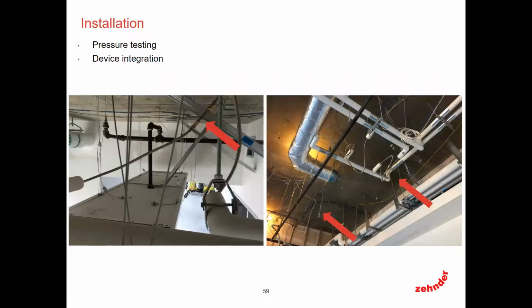So on the installation side, a couple notes here. Generally, when we install the panels, typically we'll see the installer install all the gripple or the hanger kits first. So they'll go through, shoot the deck, and then they go back and install the panels. On the left, you can see the gripple hanger kits here. And in this case, this panel doesn't have any grid around it. This was a free hanging sail panel and then had an integrated fire suppression device in it. So there's nothing else going around that.